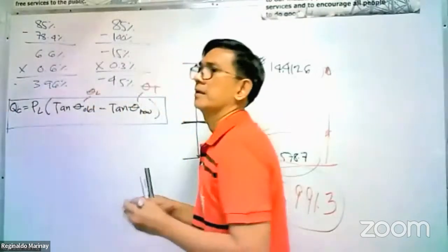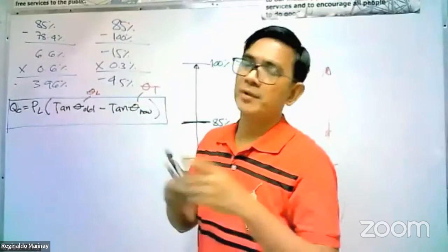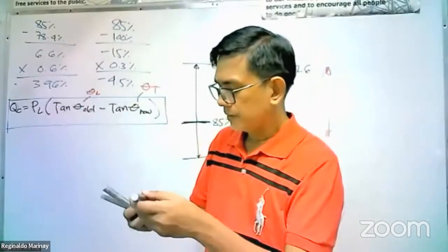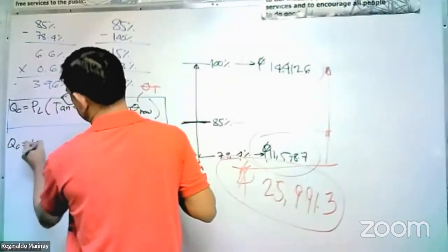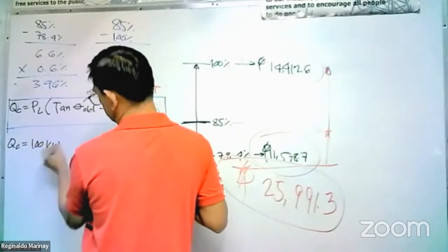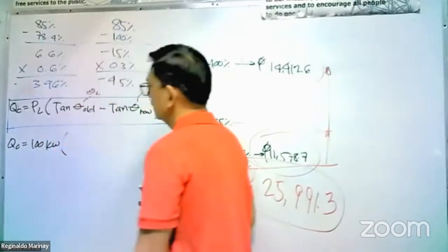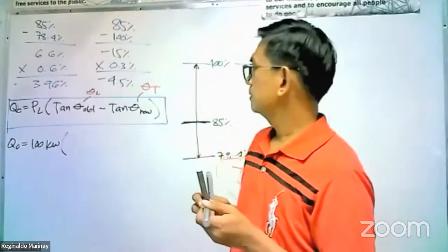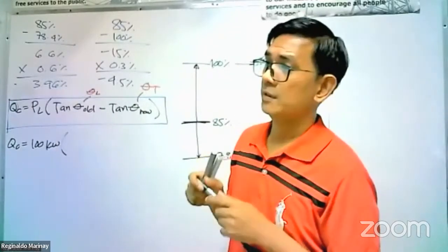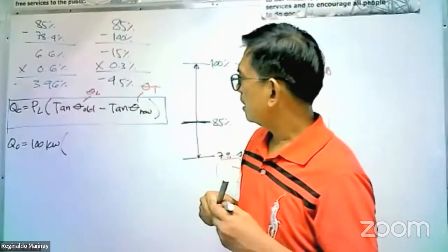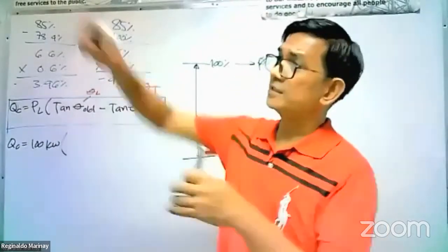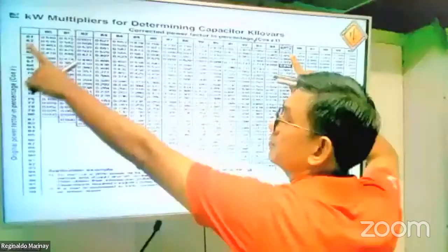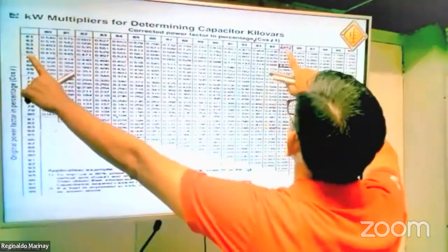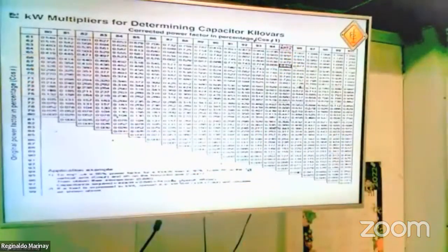For example, we have an example here. Let's say you have your QC at 100 kilowatts, then your tangent theta old minus tangent theta new. Let's say your initial power factor for this case goes from 65% to 95%.